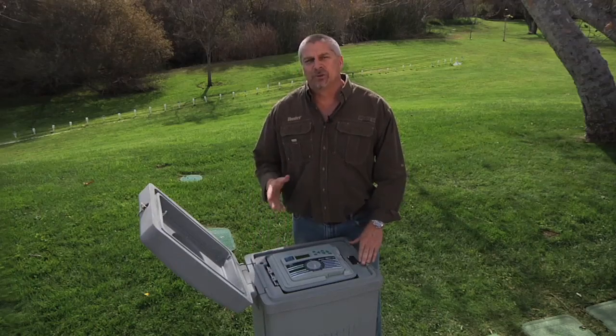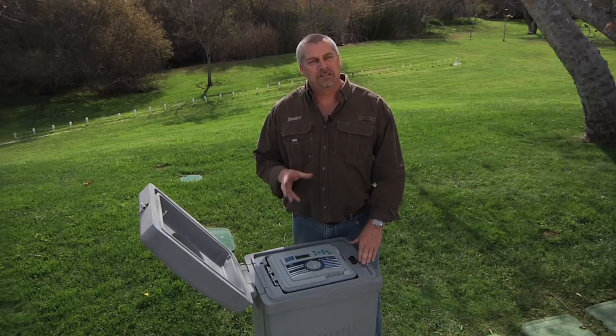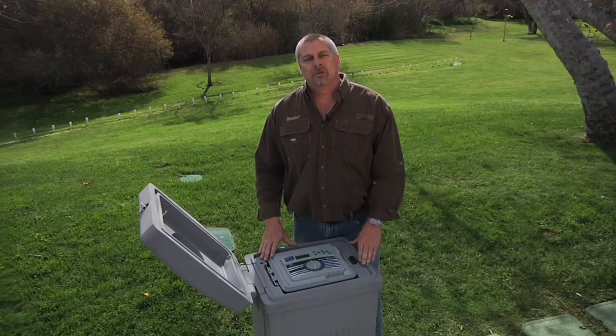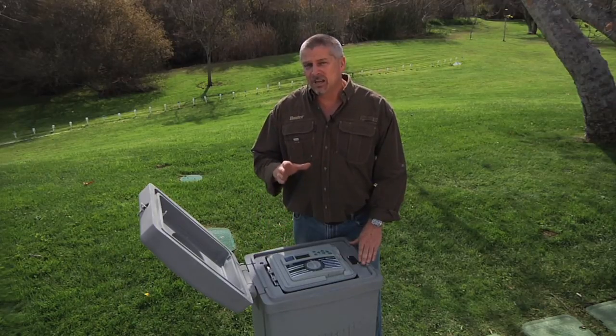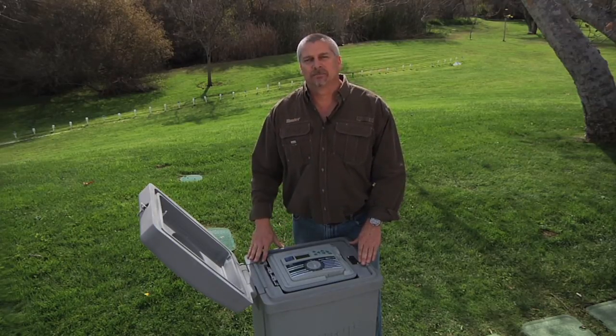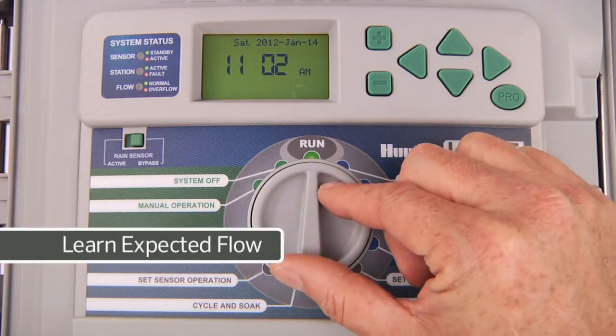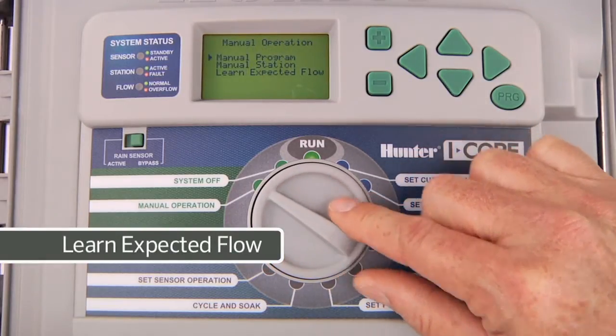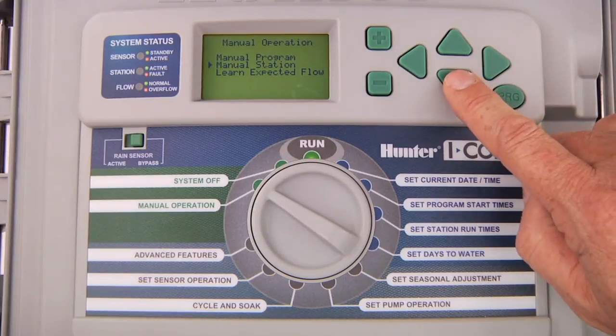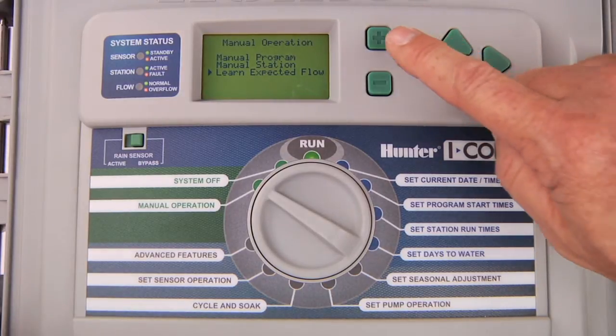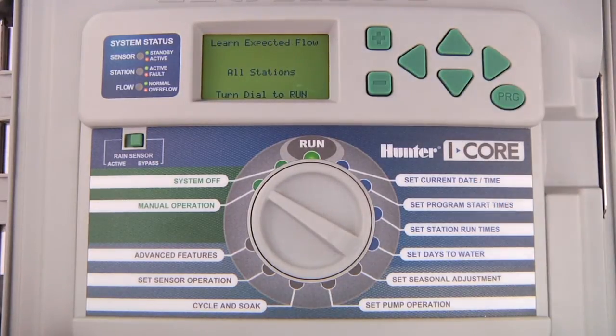So in order for the controller to learn the flow for each of the stations that you choose to be monitored, they have to have a runtime. You'll need to put at least a minute on each of those stations that you want to have the flow learned. To learn the expected flow, turn the dial to manual operation, press the down arrow button to select Learn Expected Flow, and press the plus button to access it.